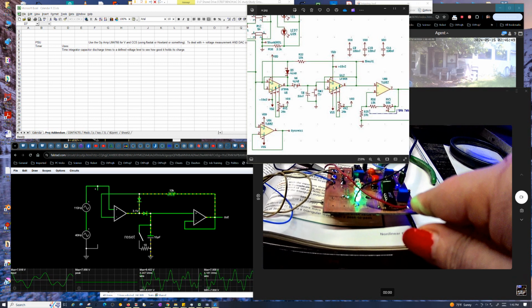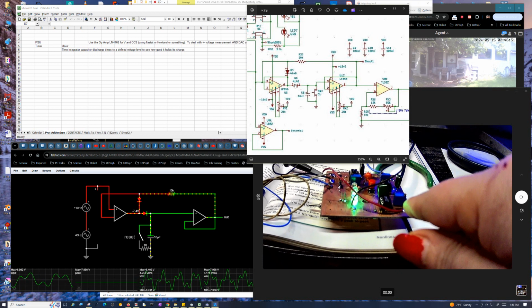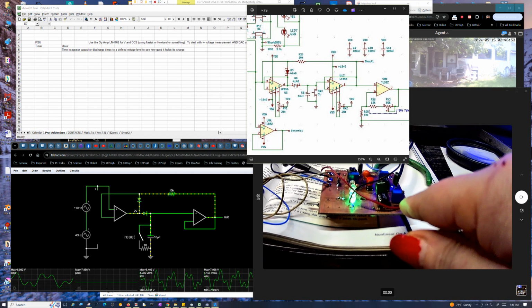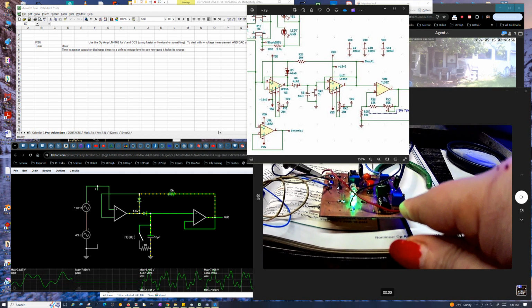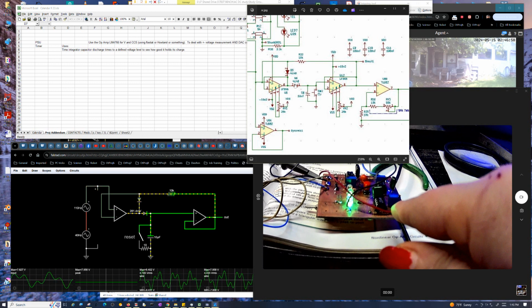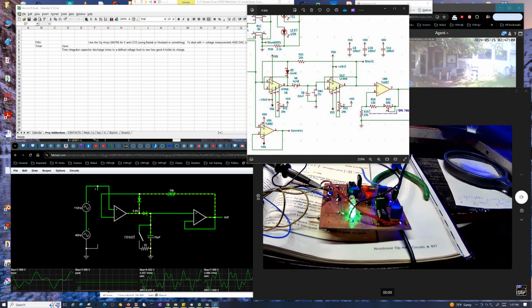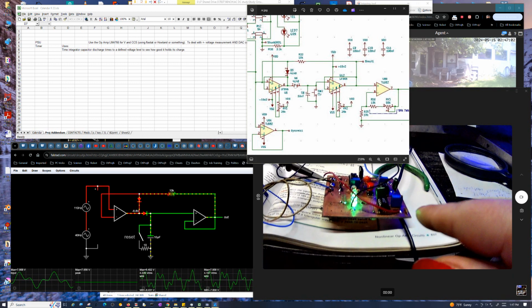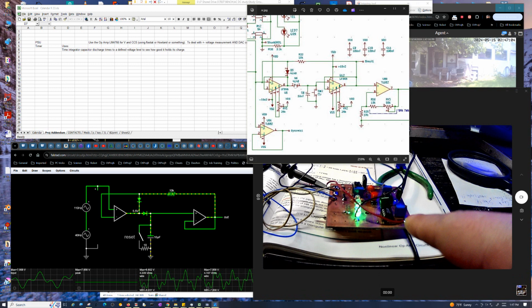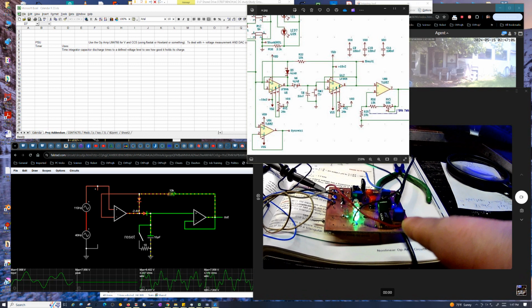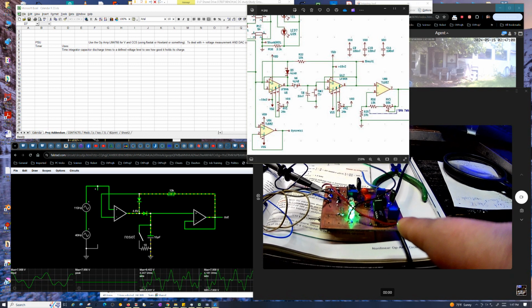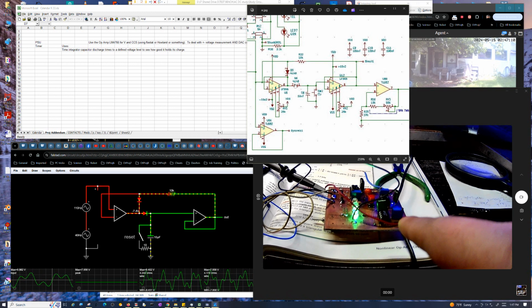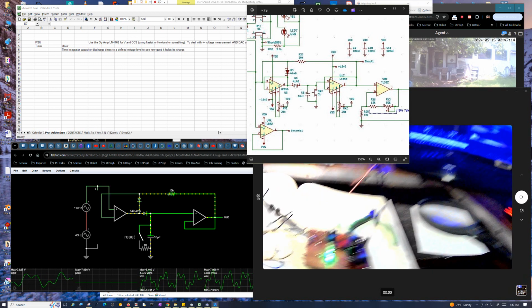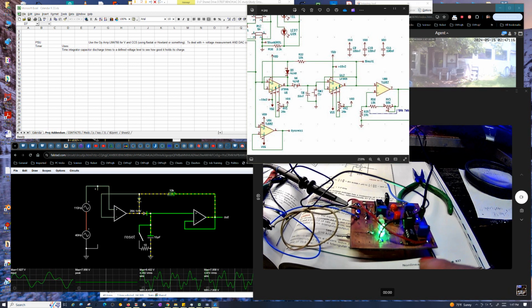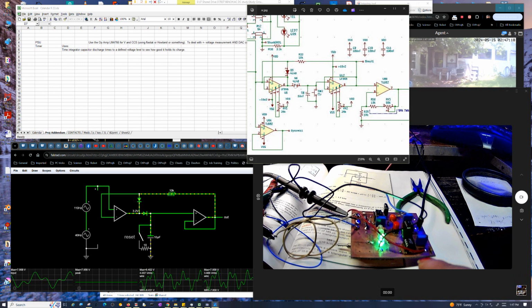That's why it has gain, 6.66 is our gain. Even the 1 millivolt error I've got right now, at a 500 amp shunt, that's like 6.66 amps per millivolt. So that's still a pretty good error, if I was looking at that and saying wow, I got 6 amps when there's no amps flowing through it, when it's grounded.